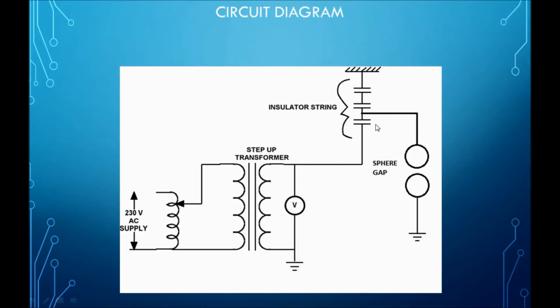But for calculating string efficiency, I require the measurement of the voltage across this unit. So how do we measure it? The voltage across the whole string minus the spark gap voltage gives the voltage across the disc nearest to the high voltage. How to measure the voltage through the spark gap? You can see the spark gap connected here. This point's voltage appears at this sphere, and this is ground. Let your spark gap distance be 1 cm.